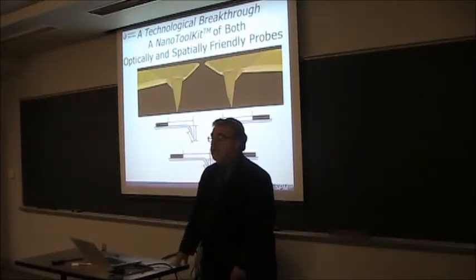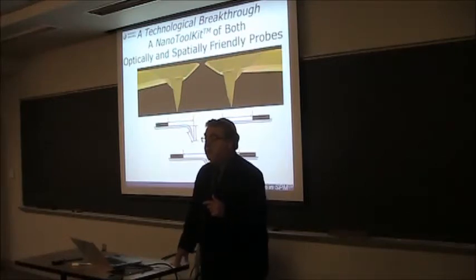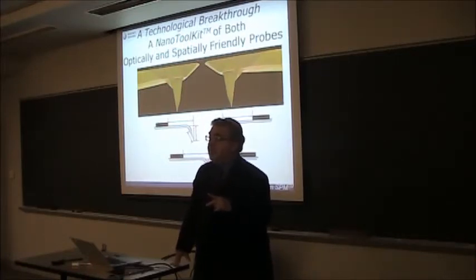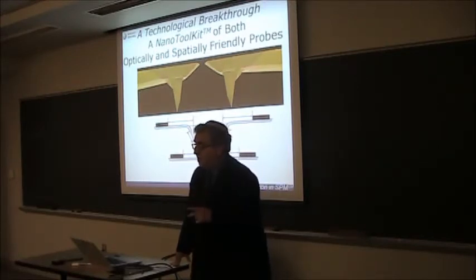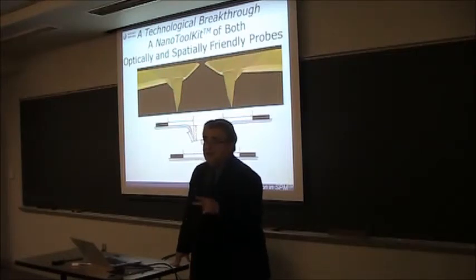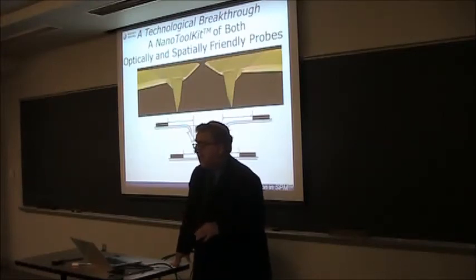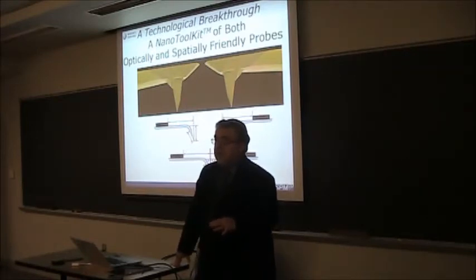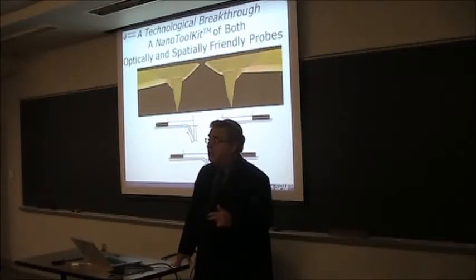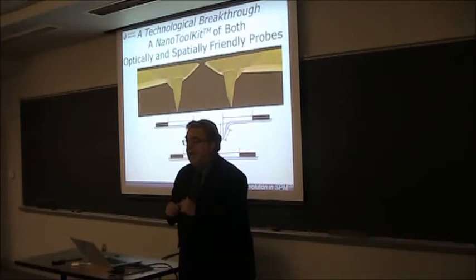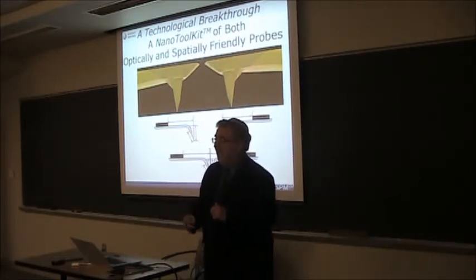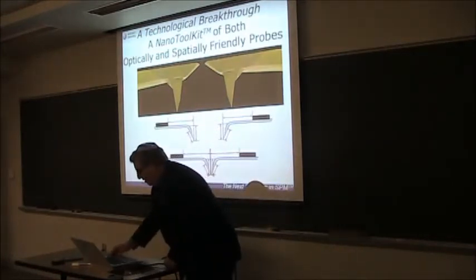So the bottom line is that there is the Akiyama probe, but I must tell you that the Akiyama probe is not very good for soft samples. The reason is that the Akiyama probe has a very large oscillation amplitude. You can only use the Akiyama probe with an oscillation amplitude of 1 micron, okay? So it's a huge force that you bring onto the system when you have such a large amplitude in the probe. So basically with soft samples you can forget about the Akiyama probe. So the bottom line is that the generality of normal force sensing with a tuning fork is still only with these probes, and also Akiyama probes do not have any other functional probes, which are very critical for doing the type of multi-probe experiments that you see are possible.